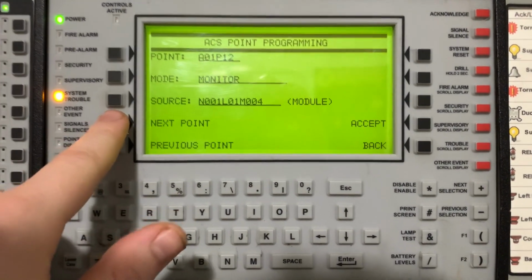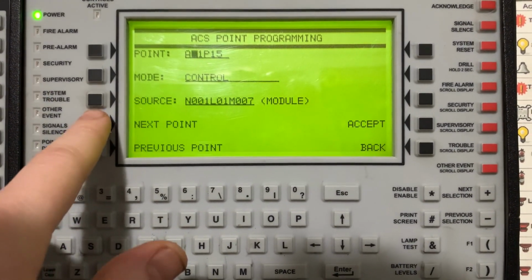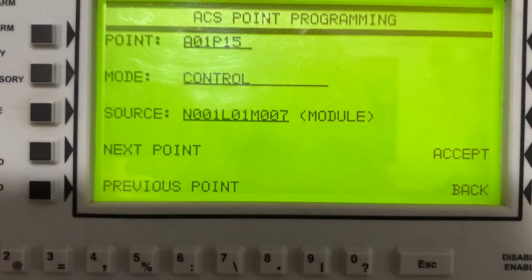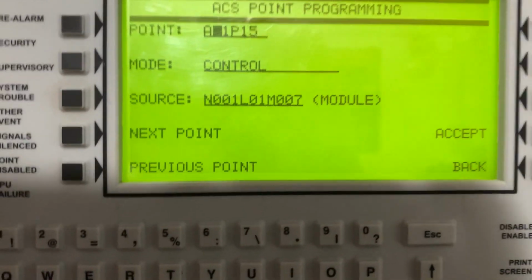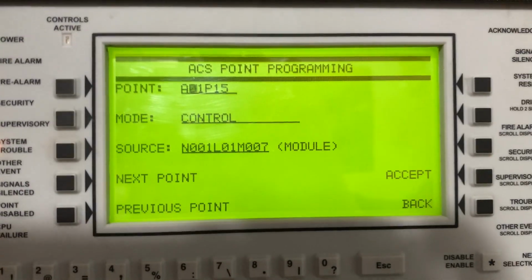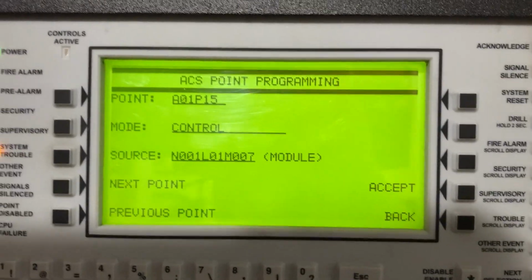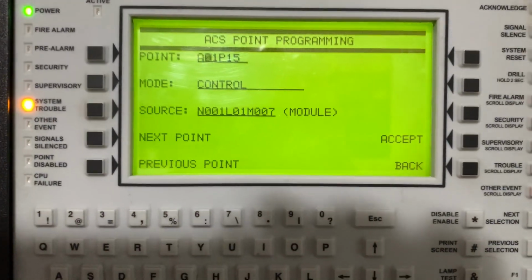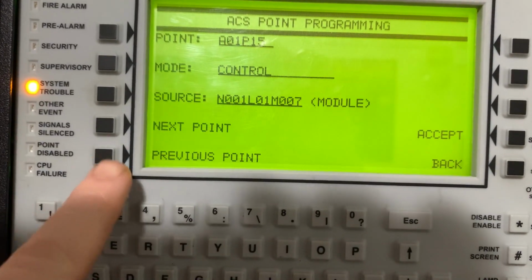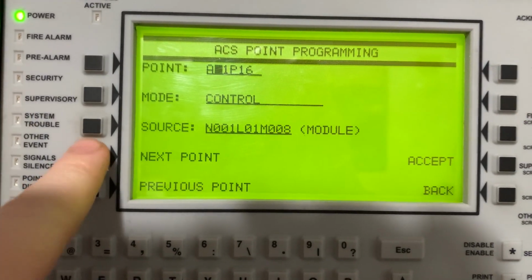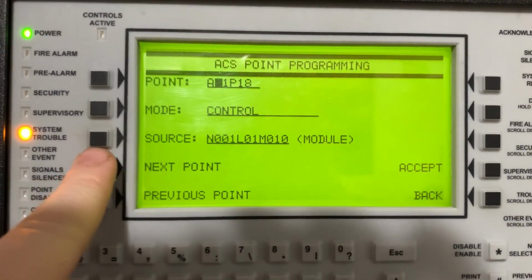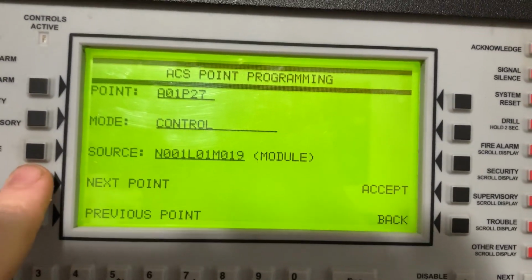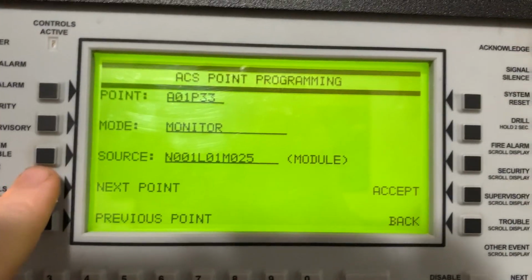So here's all the points. By the way, for control and relay modules, you have to set them to control. Otherwise, when they go into alarm, they will report as a monitor module point, which is not right. So you have to make sure that all control and relay modules are set to control. Now if we go here, as you see, here's all the modules that are added into the NCA2.